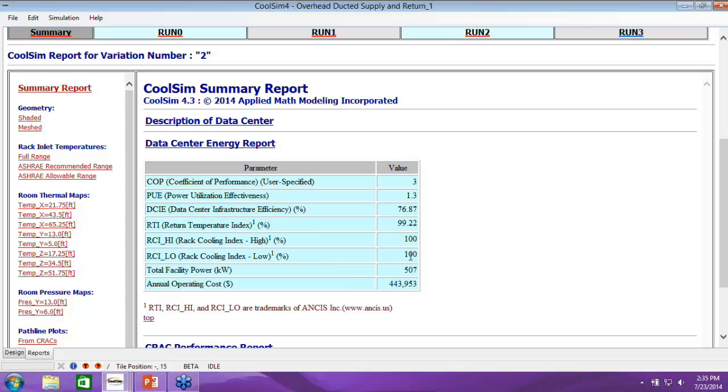Beautiful. You can see that, Paul, that when you manage to get the RTI closer to 100, the energy metric went with it. Right. And that's quite common actually, because obviously when the RTI is much less than 100, it means that you have bypassed all those.